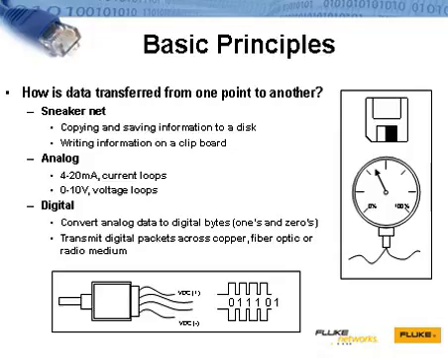Data can be transferred through different means. In today's environments, we see analog and digital. If we talk about this in terms of end devices, this distinction is very clear. Analog I/O provides an analog voltage or current that is directly proportionate to the unknown input, making it possible for a controller to measure the voltage or current, then derive its value. For example, a level sensor might output a current of 4 milliamp to 20 milliamp, where 4 milliamp might be the vessel is empty and 20 milliamp full.